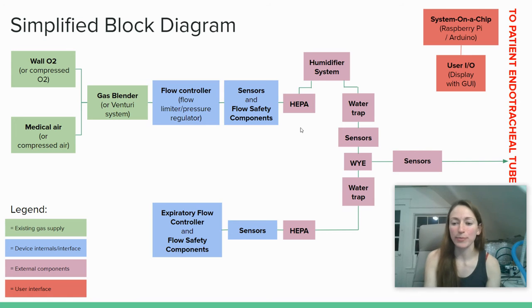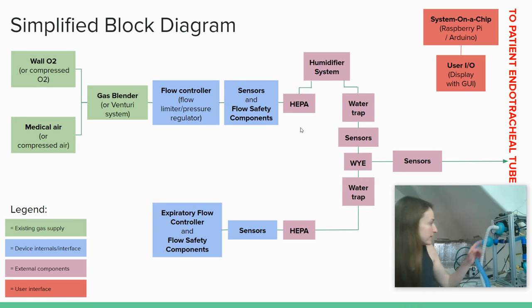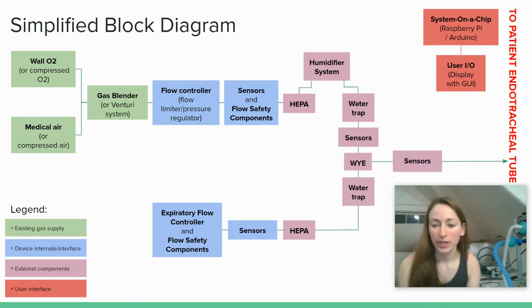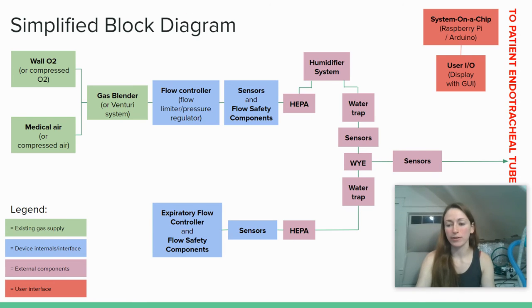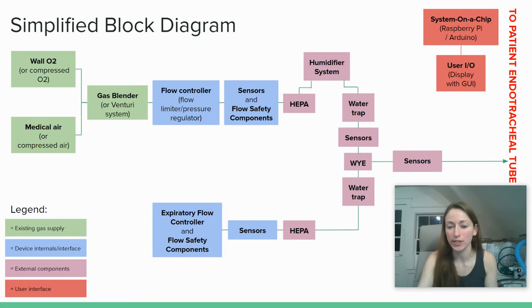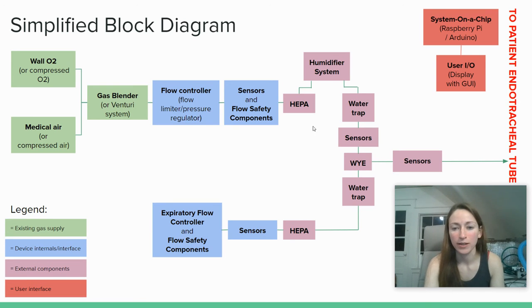So we have things like HEPA filters. If you look at my box, that's these green DAR filters to prevent contamination by the patient of the device or into the externals within the room. From the HEPA filter, we have some type of humidification system. This may be a heated humidifier or an HME. That's a heat and moisture exchanger. And then we move into the water traps to collect any condensing water to prevent pseudo-drowning of the patient. That would obviously be bad.